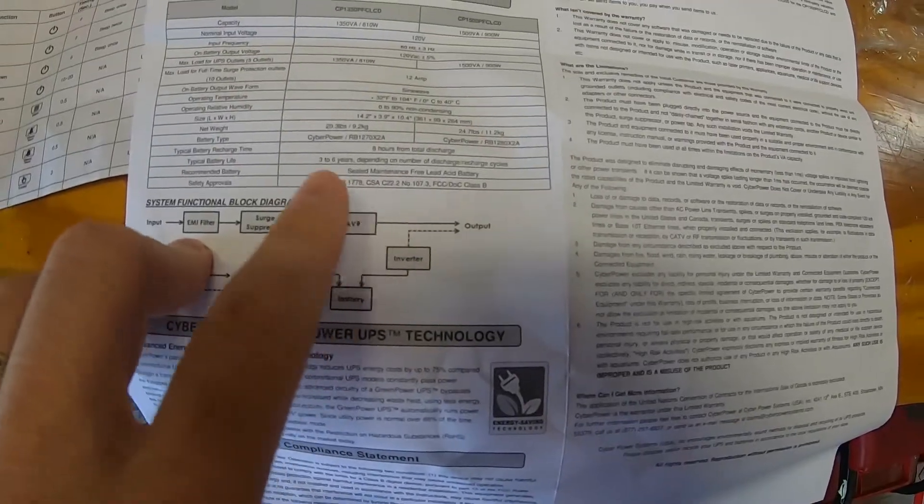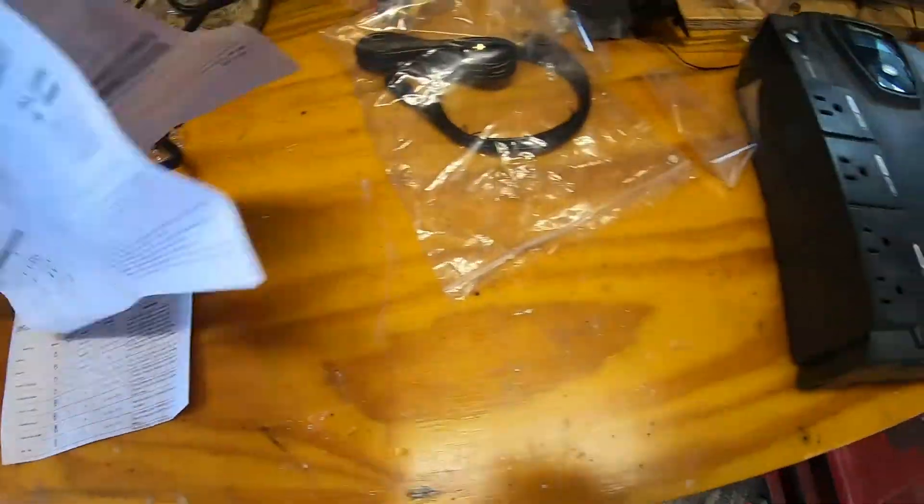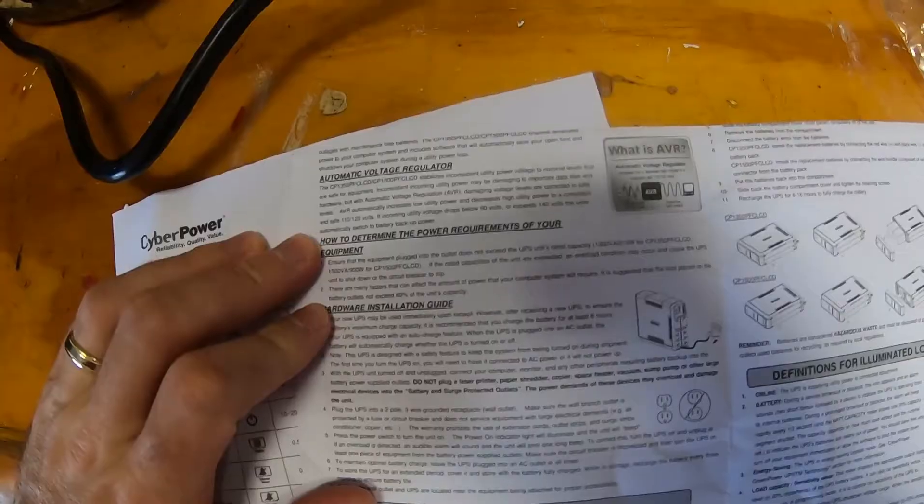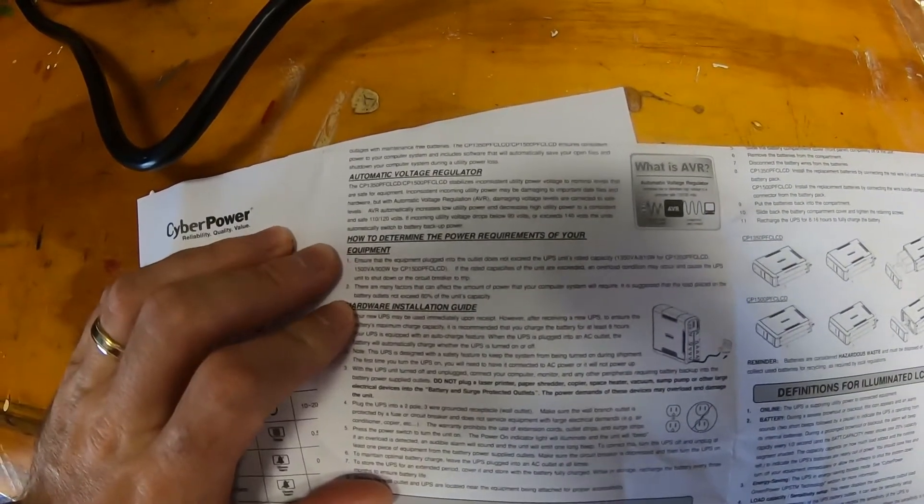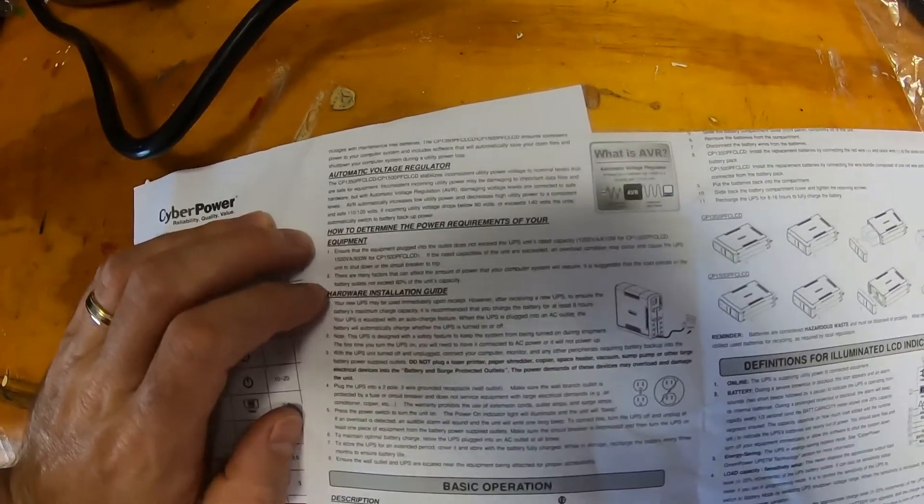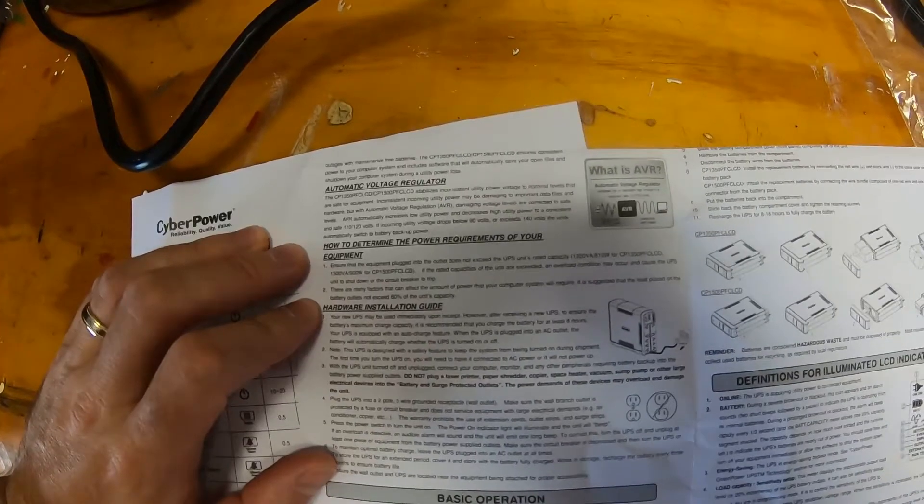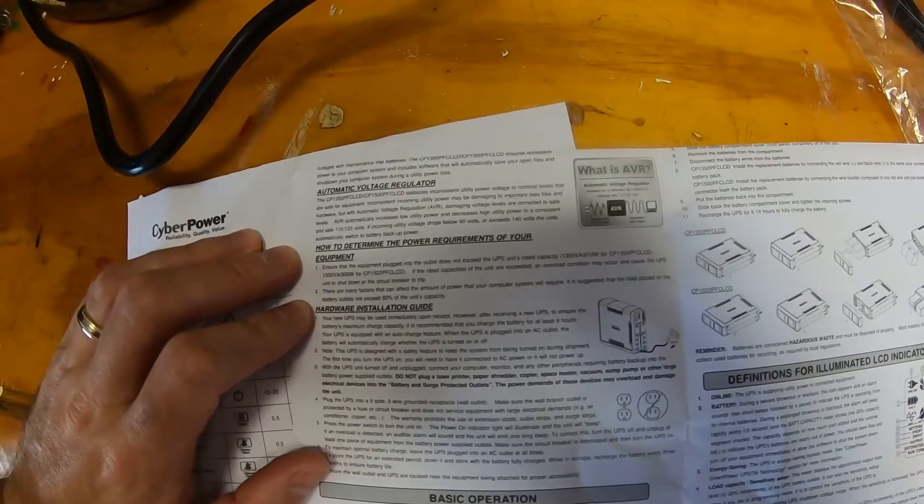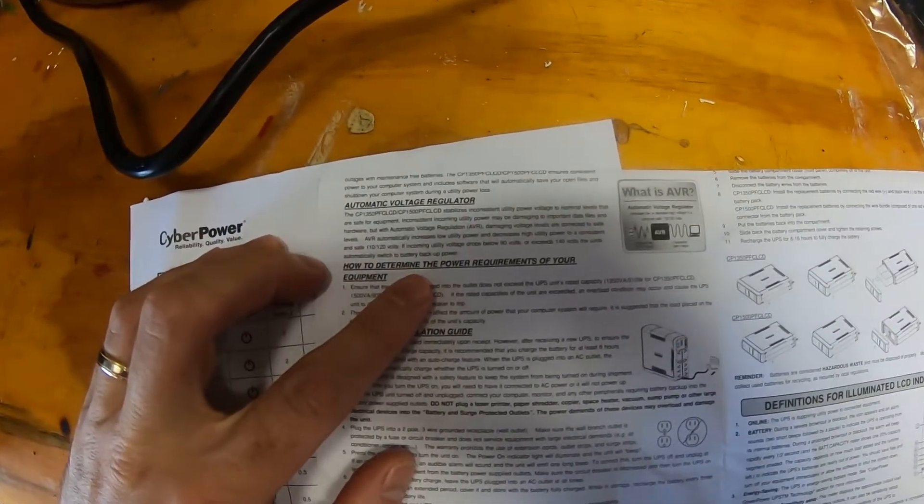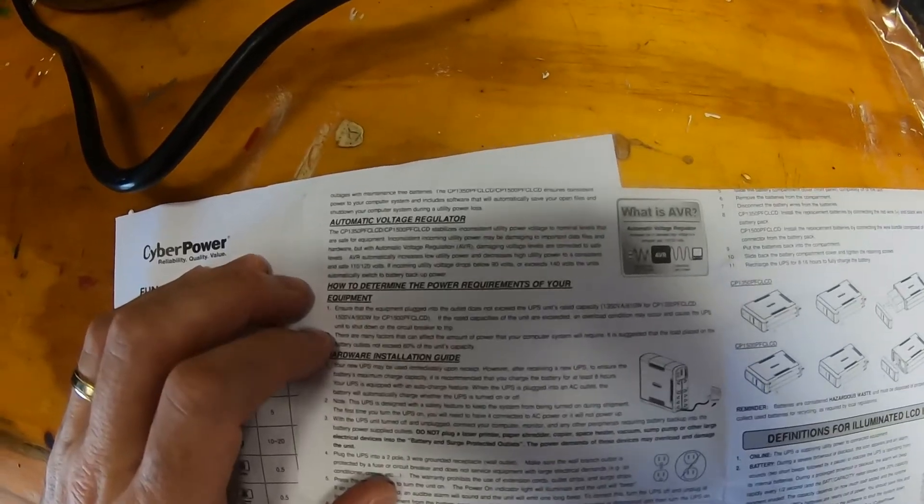Now it does say it has AVR. Which does suggest that at least here that it does condition utility output. Let's see if we can find more about that in here. What is AVR? It stabilizes inconsistent utility power voltage to nominal levels that are safe for equipment. Inconsistent incoming utility power may be damaging to important data files and blah blah blah. AVR automatically increases low utility power and decreases high utility power to a consistent and safe 110 to 120 volts. If incoming utility voltage drops below 90 volts or exceeds 140 the unit automatically switches to battery power.